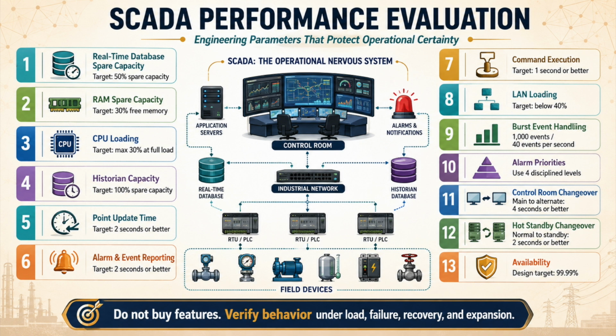This is why SCADA performance evaluation must never be treated as procurement paperwork, feature comparison, or vendor compliance language, because the real purpose is not to confirm that a software platform has screens, alarms, reports, trends, clients, redundancy, and historian functions. The real purpose is to prove that the delivered architecture performs under normal load, peak load, abnormal operation, communication failure, server failure, recovery, cybersecurity constraints, operator concurrency, and future expansion.